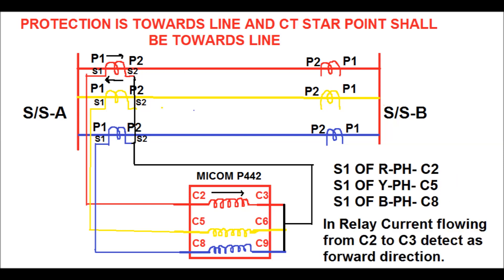When current flows in the primary side of the red phase in the direction from P1 to P2, current will flow in the secondary side from S2 to S1. In the relay, it will flow from C2 to C3 — this is the forward direction for the relay. That is, for proper polarity, P1 shall be connected on the bus side and S1 shall be connected to the C2 terminal for the MICOM P442 relay.